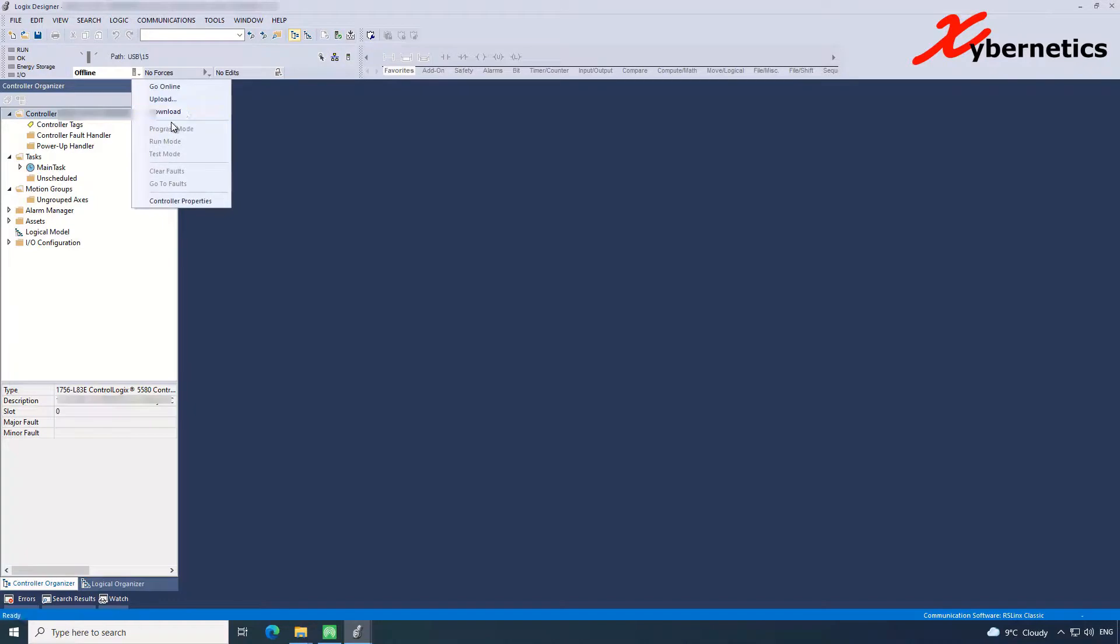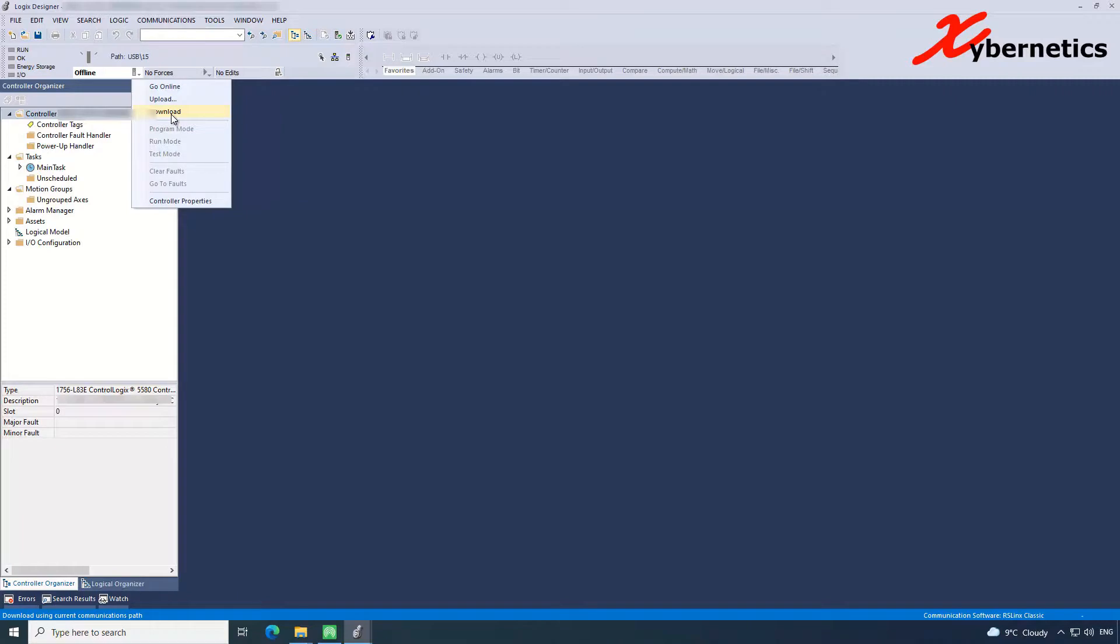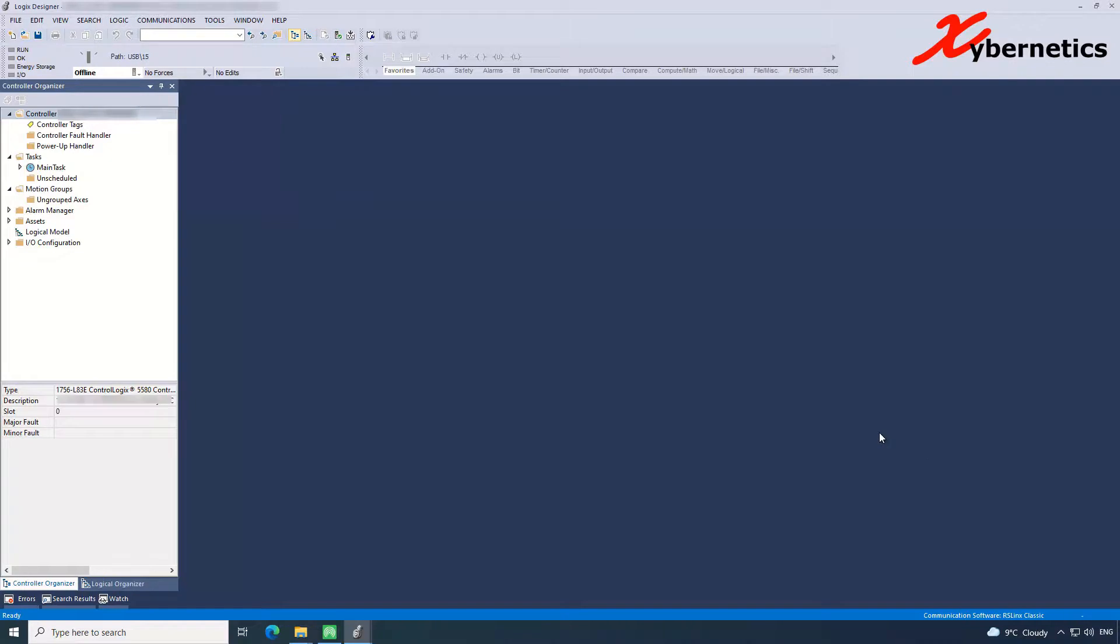The download, when you do a download, just be aware that the PLC will stop running. So any processes that need to be safe will go to ESD state. So just be careful if you do a download. This download is a full program download. You can do a download change, but it's not part of this demonstration. You can make ladder or a rung or a function block change for one or two small changes. That can be done on a live system, but you have to be online with the controller. Go to the program and make those changes.